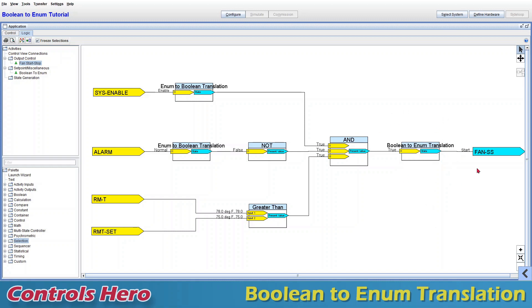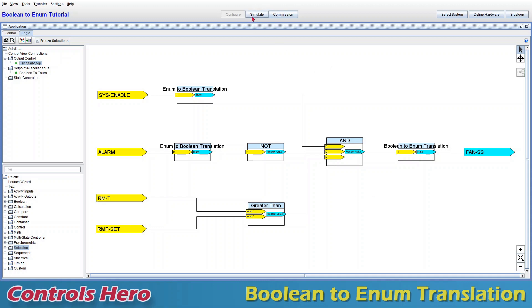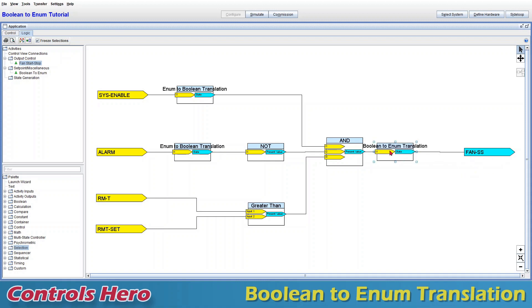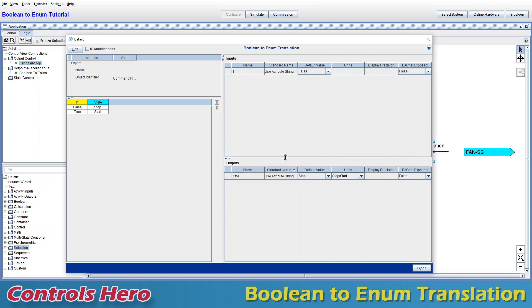That's how a boolean-to-enum translation works. Now I'm going to show you how to actually create this translation and make the connections. I've exited simulation and I'm in configure mode. I'll show you a quick way: select the existing translation, hit delete, confirm, then click my AND output and connect straight to my fan start/stop. There you go — a boolean to enum translation is auto-generated. Double-clicking shows false is associated with stop and true with start.